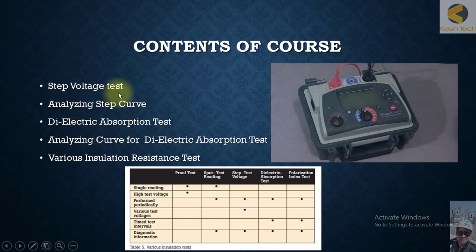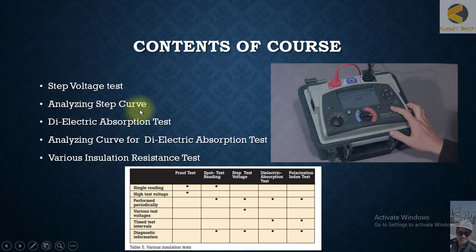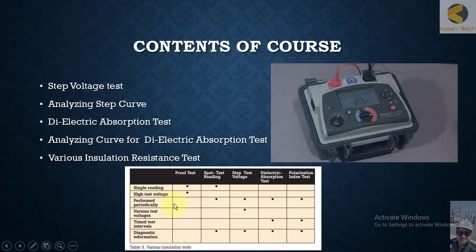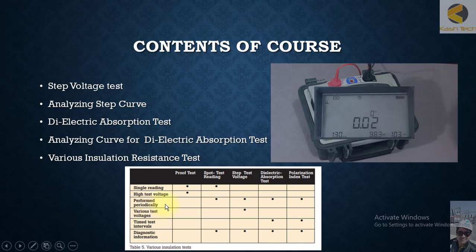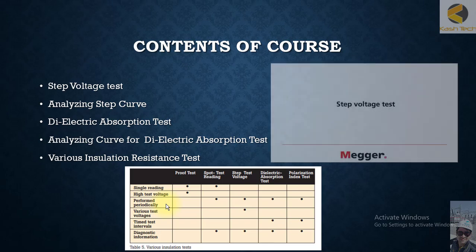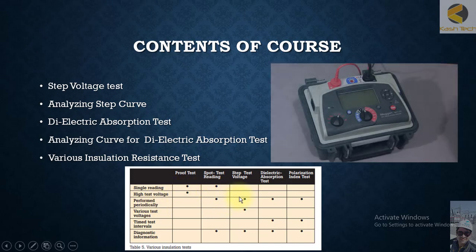The step voltage test is one of the most interesting tests developed, and we will discuss analyzing step curves and the dielectric absorption test. We will review all available insulation resistance tests: single-reading spot testing for proof testing, high-voltage testing done only at time of installation, and periodic performance tests done yearly, monthly, six-monthly, or three-monthly depending on guidelines — including spot test, step voltage test, dielectric absorption test, and polarization index test.